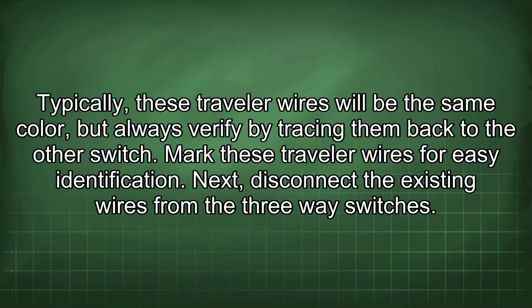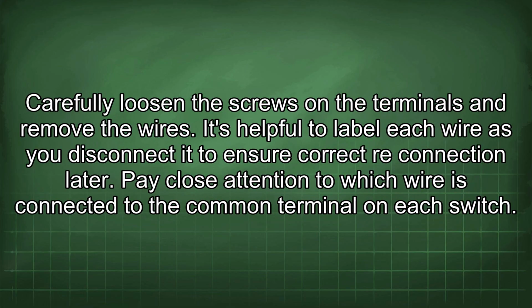Next, disconnect the existing wires from the three-way switches. Carefully loosen the screws on the terminals and remove the wires. It's helpful to label each wire as you disconnect it to ensure correct reconnection later. Pay close attention to which wire is connected to the common terminal on each switch.